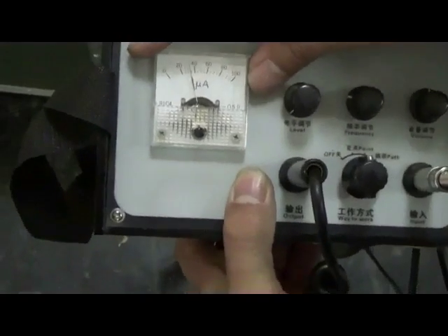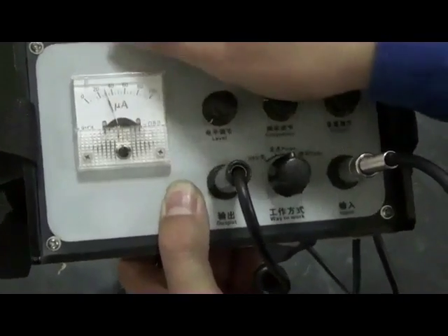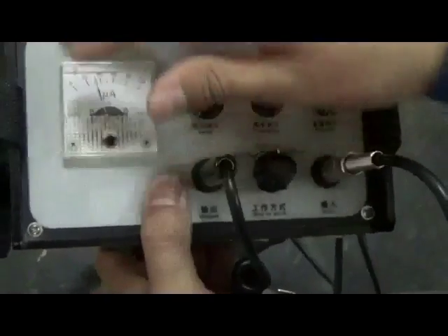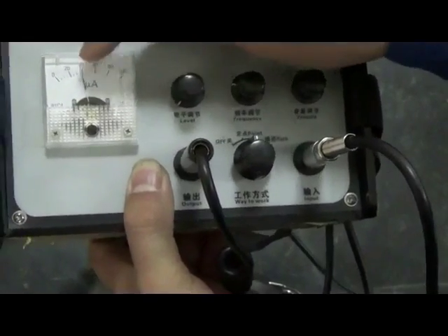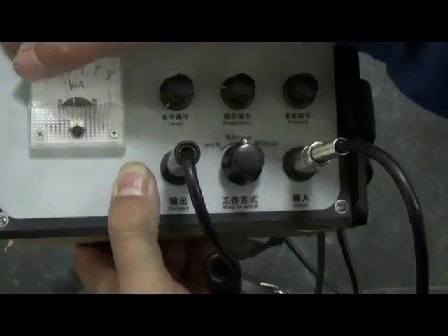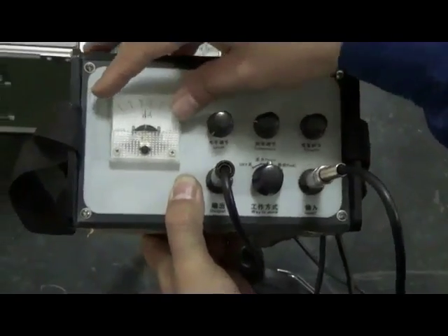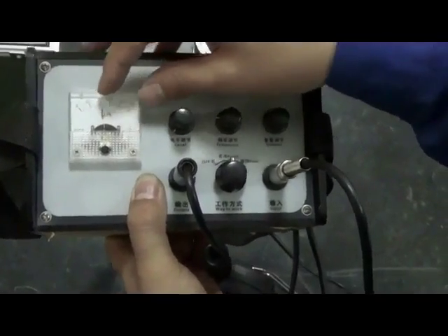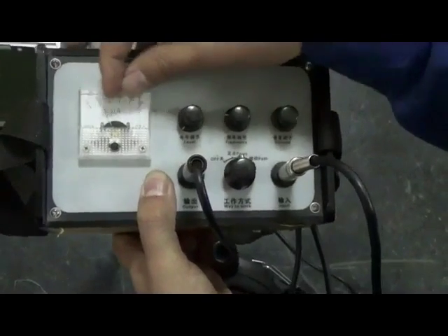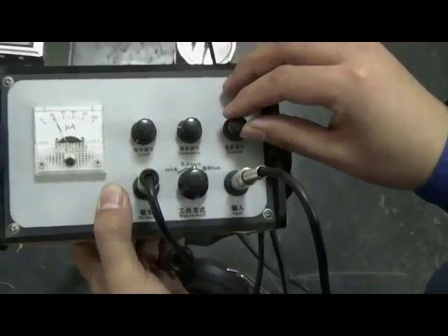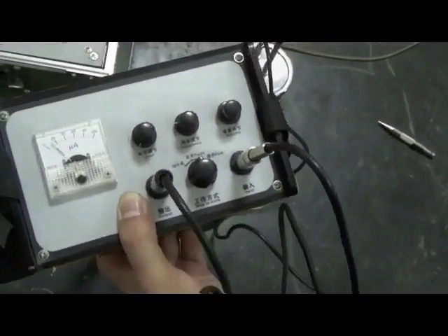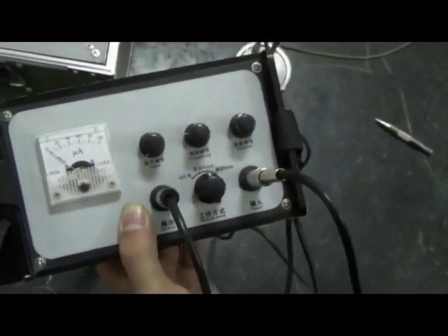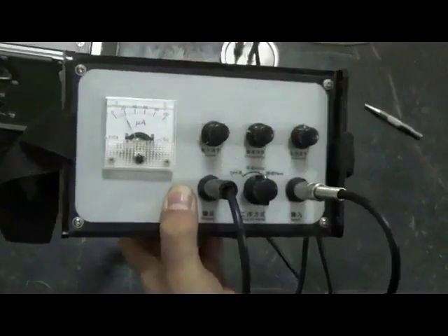In process of detecting fault, this meter will help us keep correct detection direction. If indicator is not swinging, that means you got the wrong route. So we must keep maximum swing rate in process of detecting. Adjust the volume to listen to fault by phone. The volume is maximum right above cable fault.